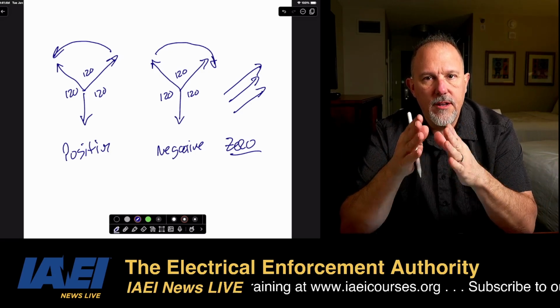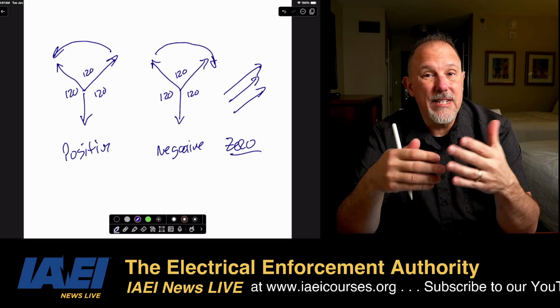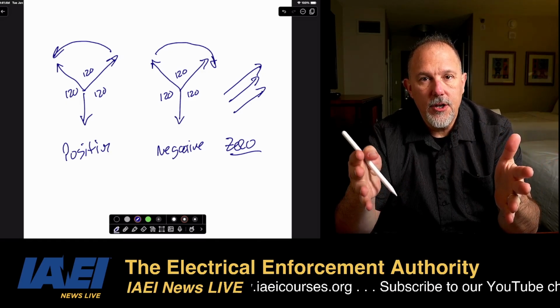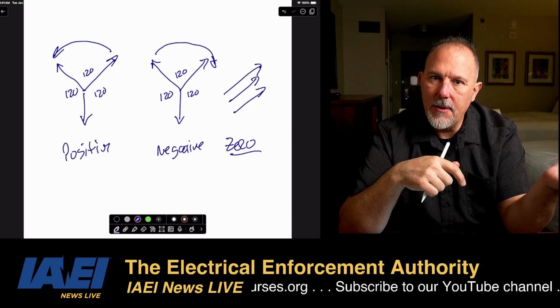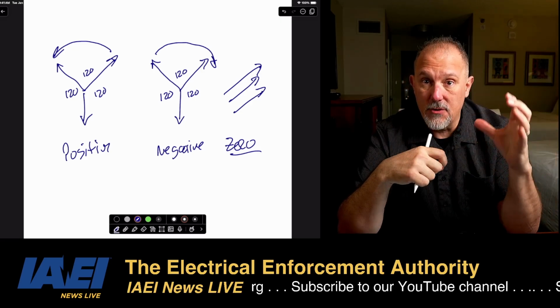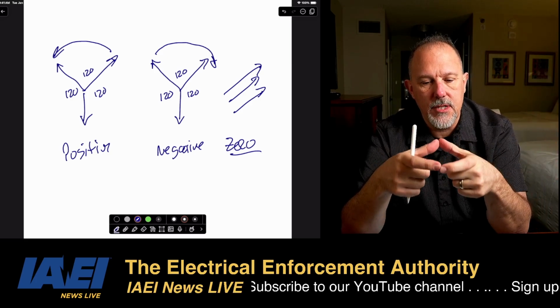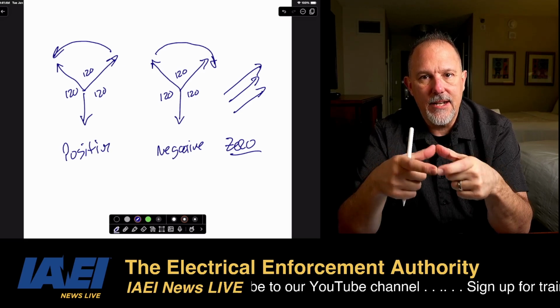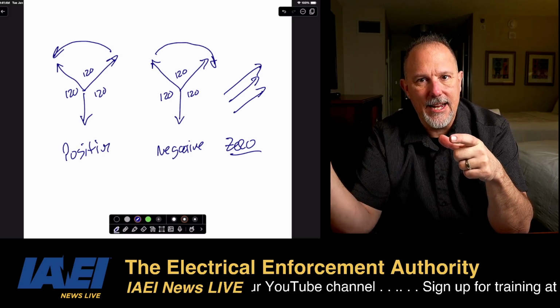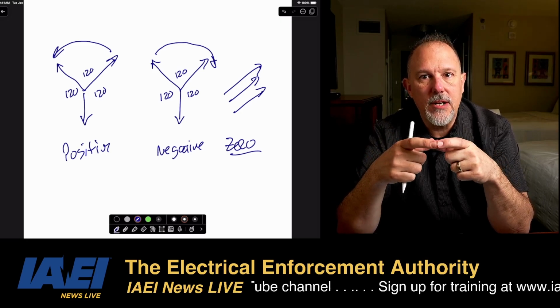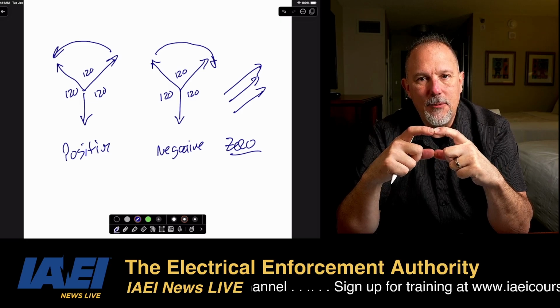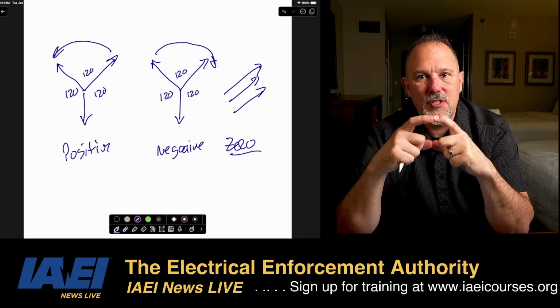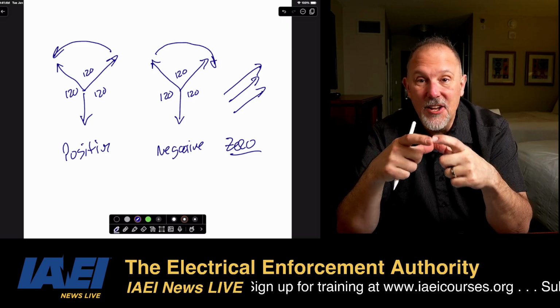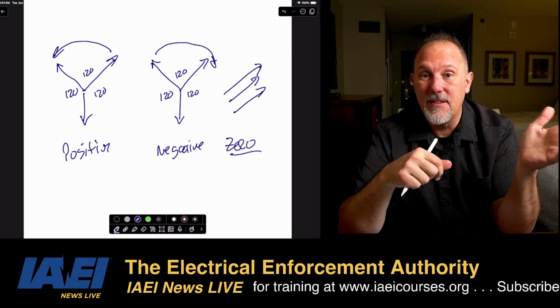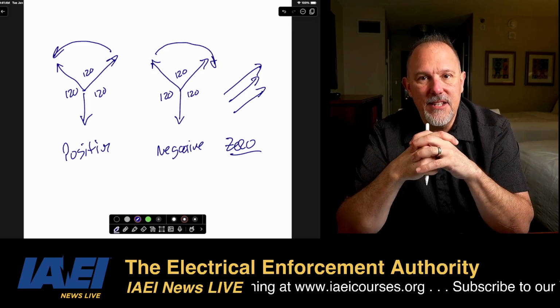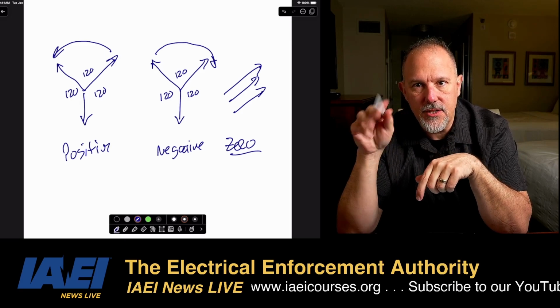Zero sequence currents are all in phase with each other. That's why they will not flow through a delta. If you have a delta-wye ground transformer, ground faults on the secondary do not show up on the primary. They'll show up as a phase-to-phase fault on the primary, but not zero sequence. So if you have a zero sequence relay on the primary of a delta-wye ground transformer, and you have a ground fault on the secondary of that transformer, it's not going to trip because it will not see a difference, because it will be all positive. There will be no zero sequence currents. The zero sequence CT will not detect zero sequence currents on the primary of a delta-wye ground transformer because zero sequence currents will not flow through a delta. They just circulate in the delta.